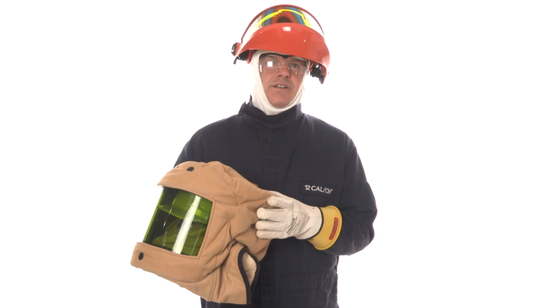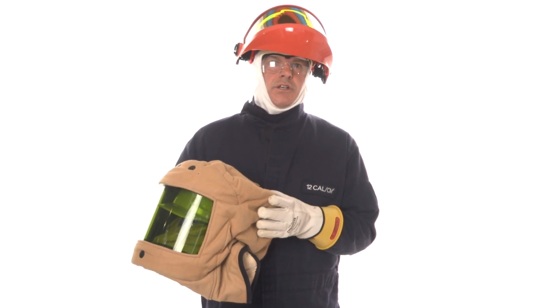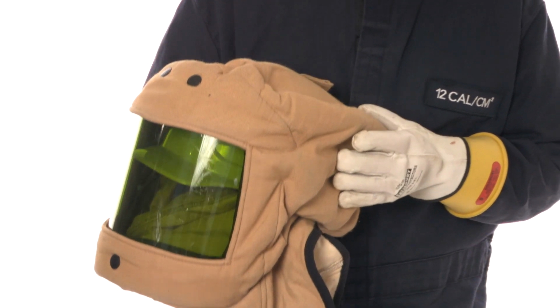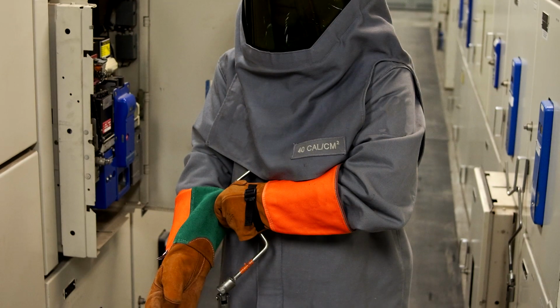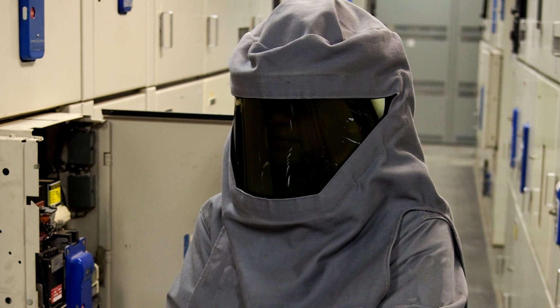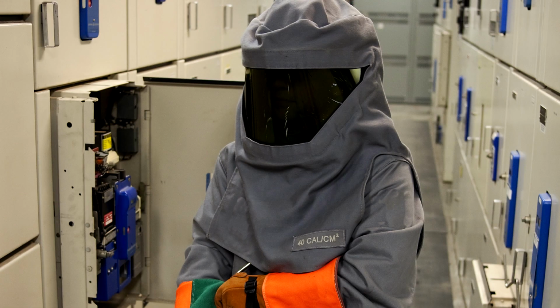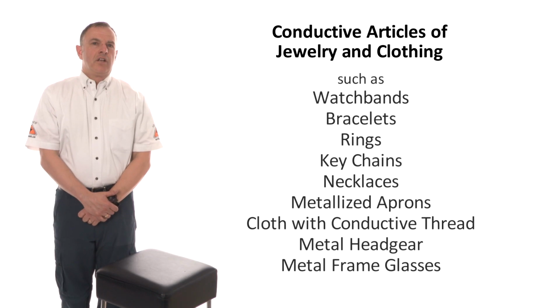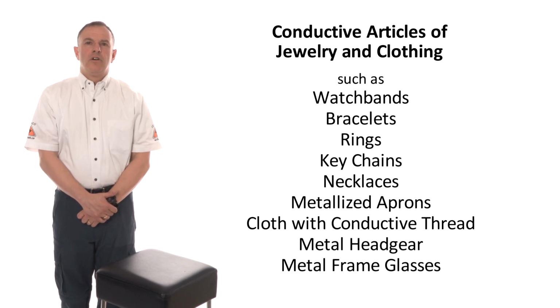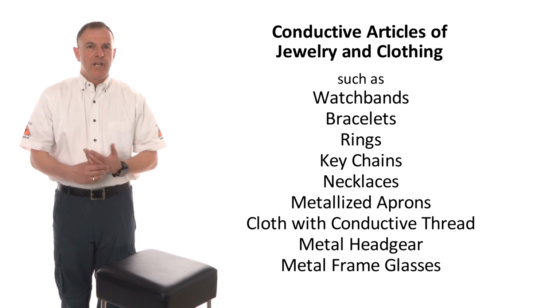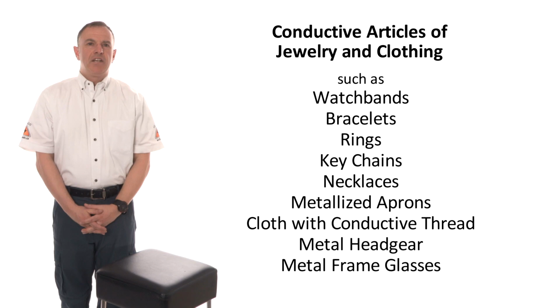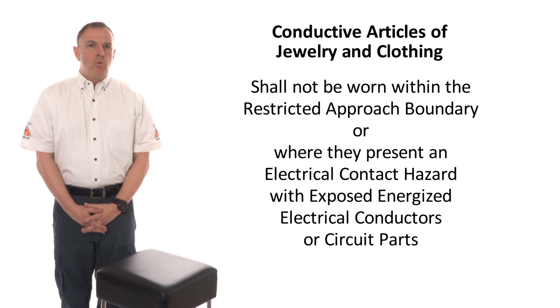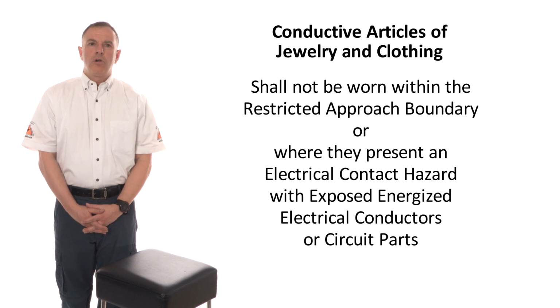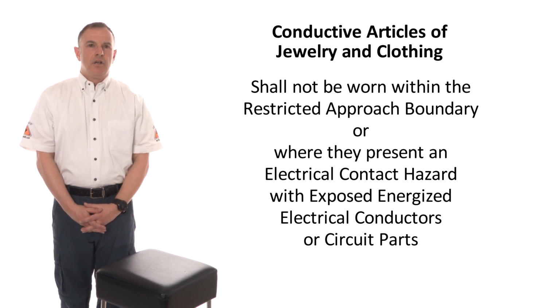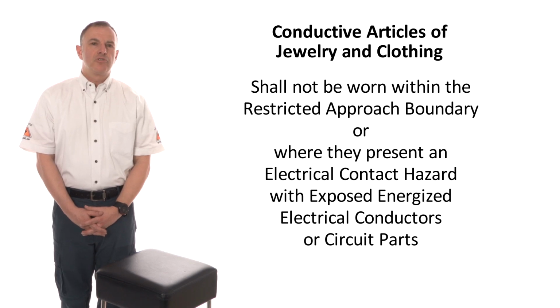For the head, face, neck, and chin protection, from the thermal effects of an electric arc flash, the use of an arc-rated face shield or arc flash suit hood with an identical or higher arc rating to the arc-rated clothing is recommended. Wearing of conductive articles. Conductive articles of jewelry and clothing, for example, watch bands, bracelets, rings, keychains, metal headgear, or metal frame glasses shall not be worn within the restricted approach boundary, or where they present an electrical contact hazard with exposed energized electrical conductors or circuit parts.